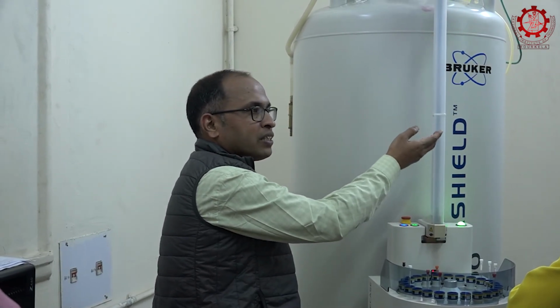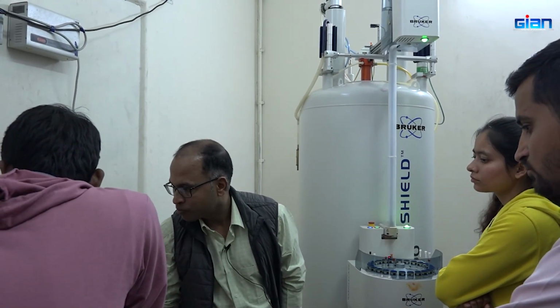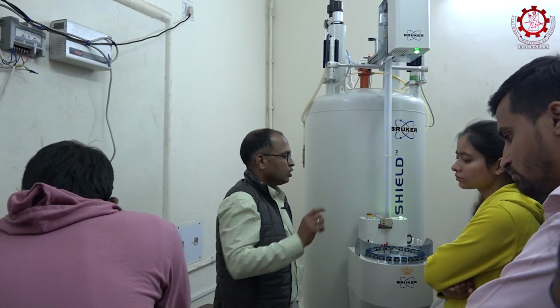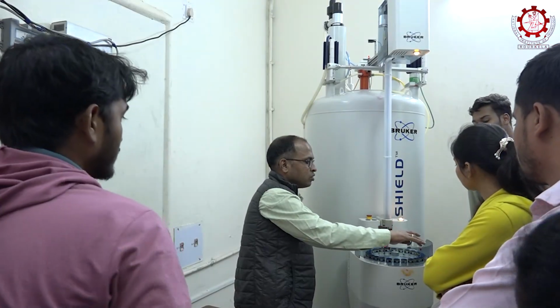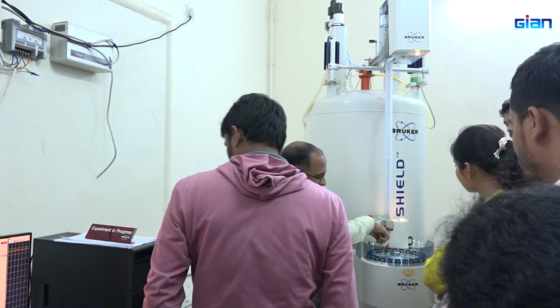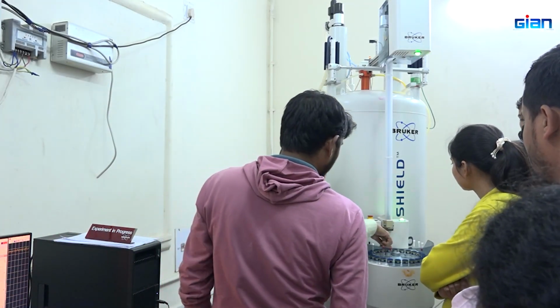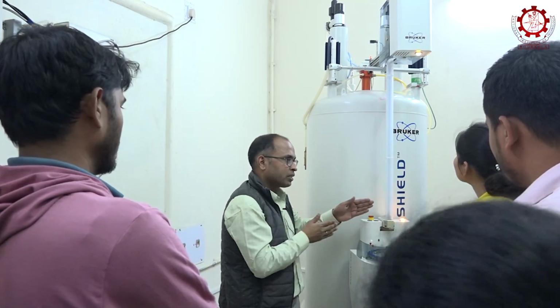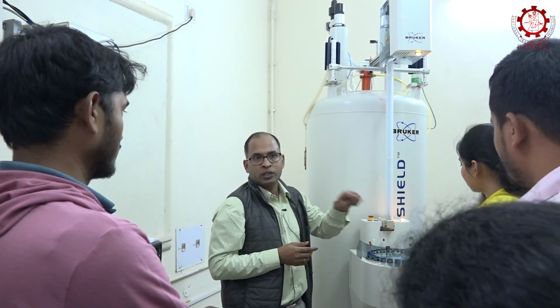If there were no pressure, it would just drop and break. Which one are you giving? SX 24. Now he will give the command to scan sample number 24. It is sensing the tube, which sample holder is there. 24 means it will continuously rotate, and at 24 it will stop.